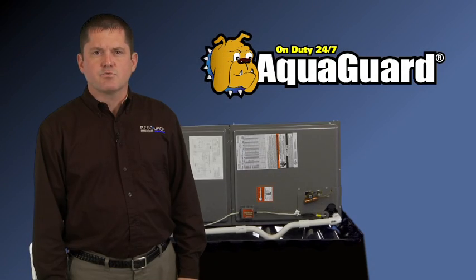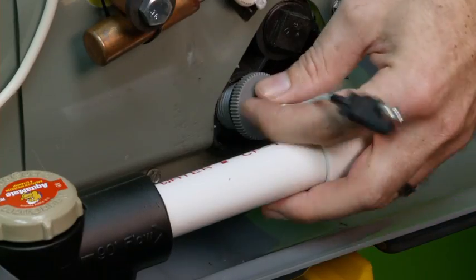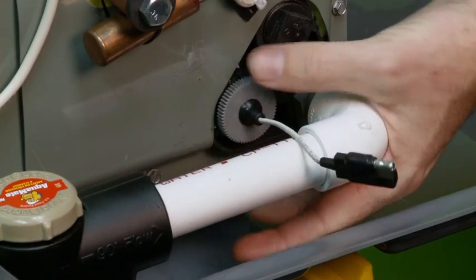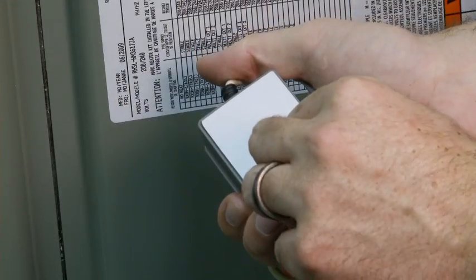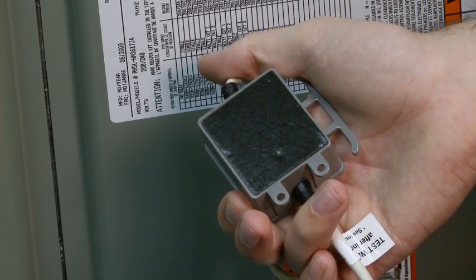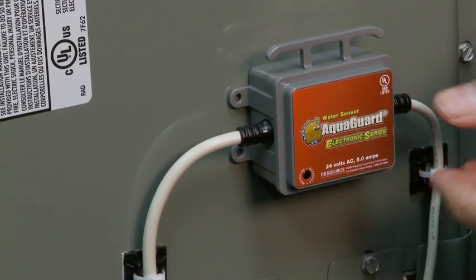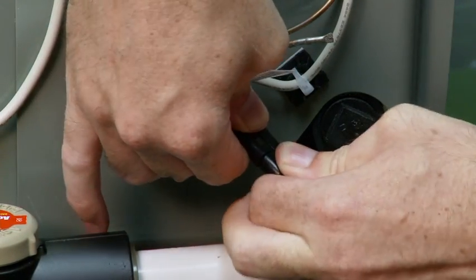The engineers at Resource Conservation Technology knew we could do it better. The 3150E's probe installs in the auxiliary drain opening of the cooling coil. Only this baby can install with less than a half an inch clearance. The polycarbonate switch body has a strong adhesive back and can be installed in any convenient space. The waterproof plug allows easy installation of the probe and access to the unit's panels.